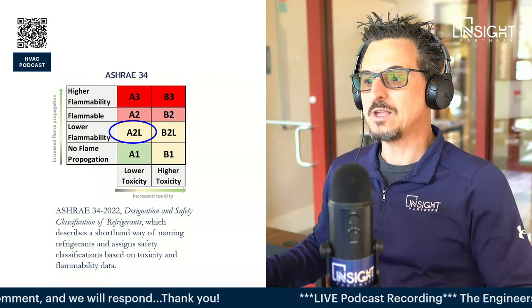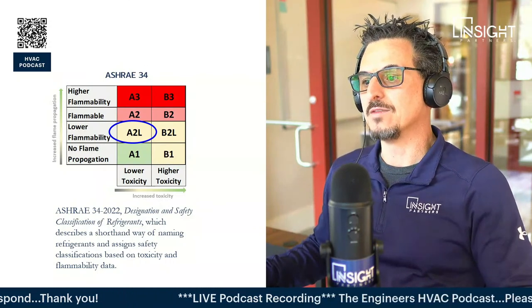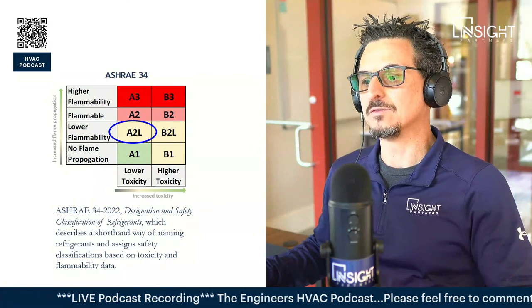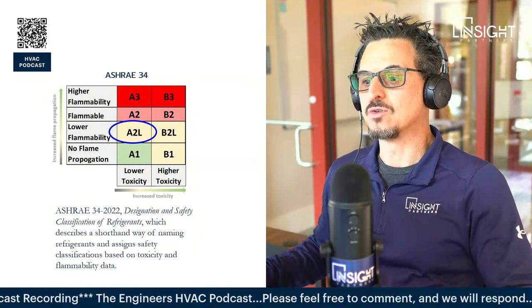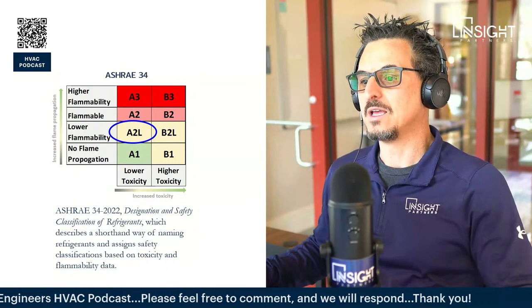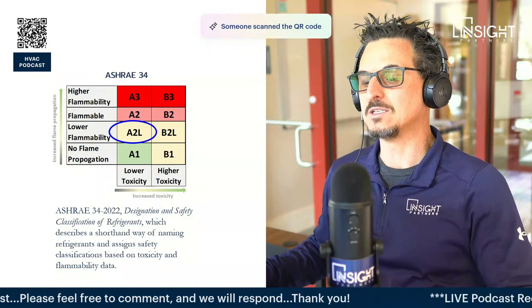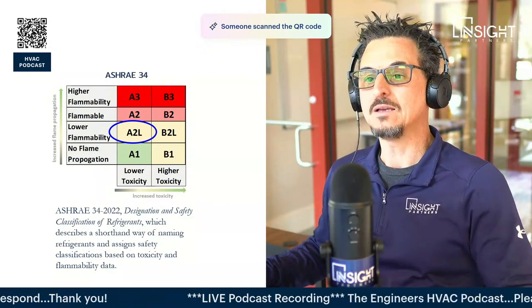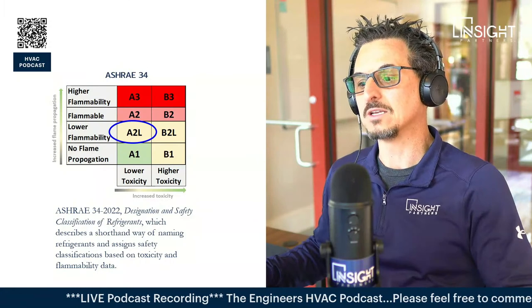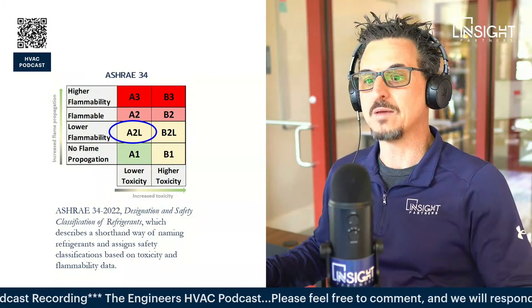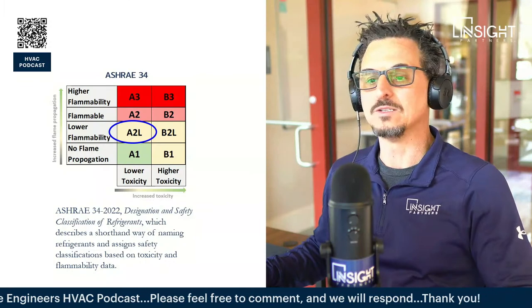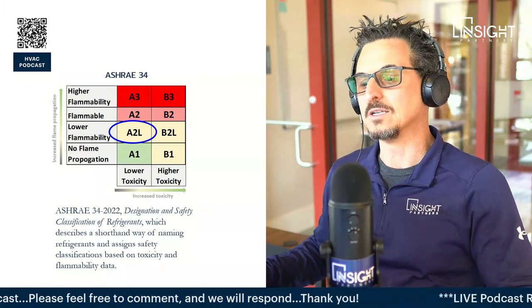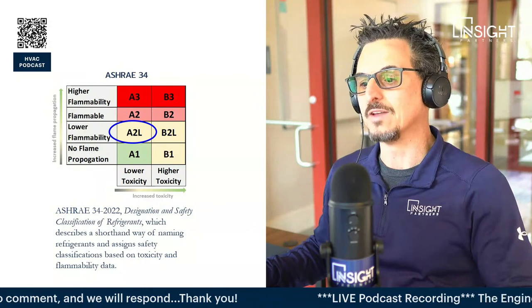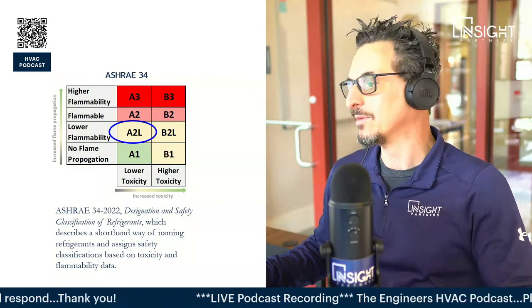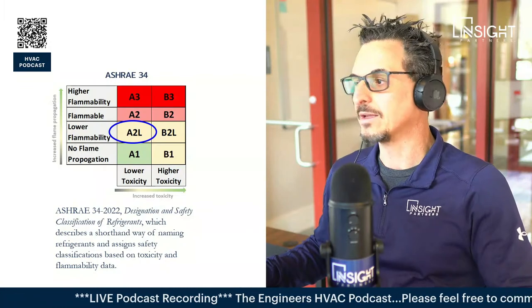ASHRAE 34-2022 is what's called the designation and safety classification of refrigerants. It describes a shorthand way of naming refrigerants and assigning safety classifications based on toxicity and flammability data. So A stands for non-toxic. 2 means it's flammable, and L means it's a low burning velocity. So 2L is what's called mildly flammable or lower flammability.